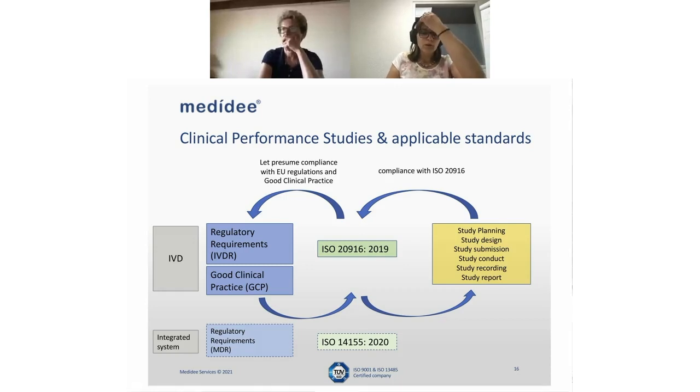Now, you've maybe heard as well of the ISO 14155. This is the standard for the conduct of clinical investigation on medical devices. So IVDs are not within this scope. However, if you have an integrated system where, for example, as part of your IVD system, you have inside a lancet or a device like this, you need as well to fulfill the requirements of the MDR for the medical device. And for certain aspects of the study, you would need as well to consider the standard on clinical investigation for medical devices.